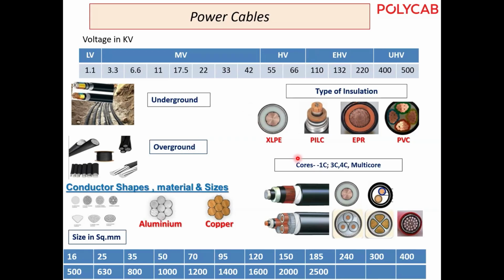Depending on the insulation, we categorize cables as XLPE, PILC, EPR, and PVC cables. XLPE is cross-linked polyethylene. PILC cables are no longer manufactured by any cable manufacturer, but for whatever PILC cables are in the system, if they fail, we have to use a transition joint. EPR cables are there and PVC cables are there. Depending on the conductor, aluminum or copper, and depending on the core, single core, three core, or multicore, we categorize the cables. Generally, sizes range from 16 square mm to 2500 square mm. The high square mm sizes are used for the extra high voltage categories, but up to 33 kV we use up to 400 for three core, or sometimes 500 square mm also. For single core, we go to 800 or 1000 square mm.